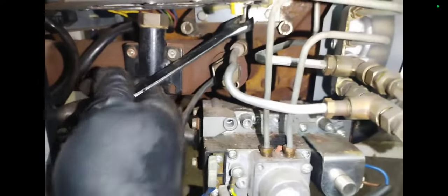So this unit here, I think, is the bottom left unit, which I was having some trouble with. So I went inside there again to inspect the burner, because I washed it down and I thought, well, where's the probe? Are the probes in a bad place? I'm going to go back and inspect this unit another time. But here you can see that I went back to have another look at it. Without these fixed spanners, I mean, you probably could use something else, but they're so tiny and ideal for getting into tight spaces. I can't imagine using, there's probably other ones. Put in the comments below what you would use down here in this tight situation.